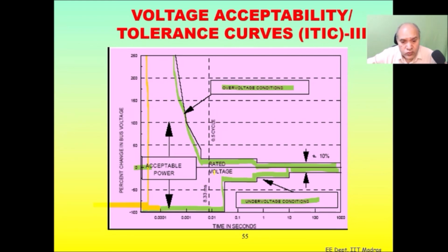However, if this goes on for a longer time, for example the same voltage is here, then it will be affected because the time is more. And V into time becomes a kind of index: a small voltage, how long? High voltage, how long? And this limit is the steady state limit. You can see it here. So once we have plus minus 10% variations here, then it can operate infinitely, on a continuous operation basis. So this is the meaning of the voltage acceptability curve.